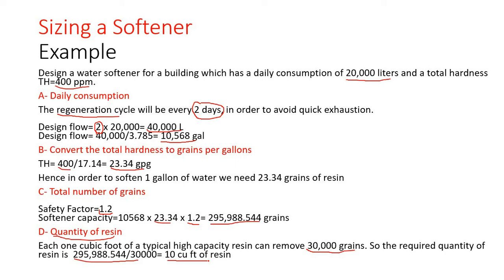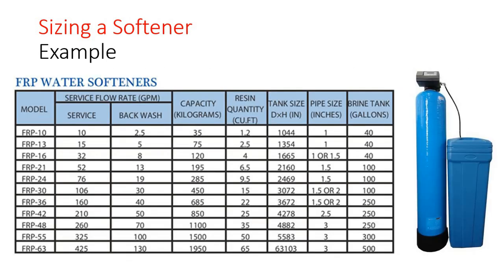10 cubic feet means 10 bags of resin. Now let's see how to choose the vessel and the brine tank. We need to get a brochure from the manufacturer and check the information in that sheet. I will go to the resin quantity we have already designed — we need 10 cubic feet. Going to this range, we will choose 15 because it's more conservative. So we need a tank or vessel that is 30 by 72 inches, and the brine tank will be 100 gallons.